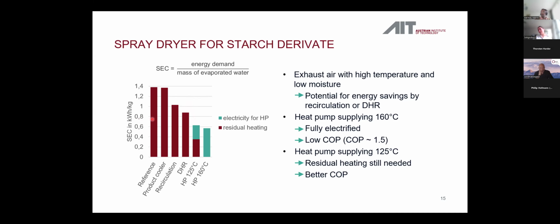to around 0.8. Then we investigated two configurations for a heat pump. The first option is to fully electrify this drying process by adding a heat pump that is capable of supplying 160 degrees Celsius, which is the needed drying temperature. But this results in quite a low COP for the heat pump of around 1.5, but leads to the lowest possible specific energy consumption.